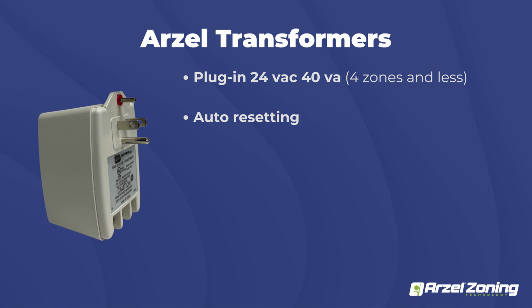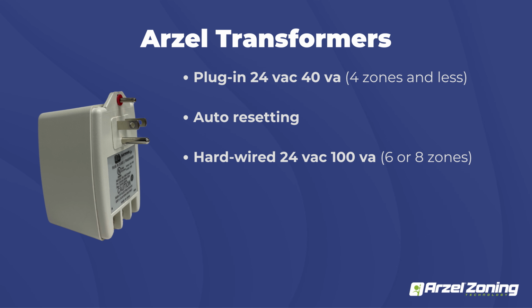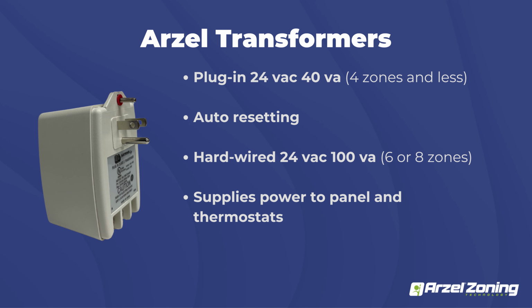If you get into 6 or 8 zone, so the 6 or 8 zone AirBoss, that actually ships with a hardwired transformer. It's 100 VA. It's 120 or 220, depending on your application. You would hardwire that, and then that would provide the 24 volts to your system to power the panel and all your thermostats. With the hardwired transformer, it doesn't have an auto resetting fuse on it, but it does have a fuse. So if there's ever a short, it trips that fuse, and then you just have to reset it with the switch on the transformer.